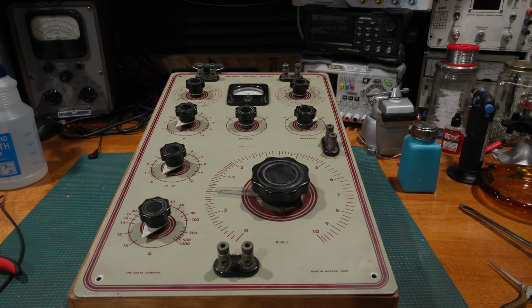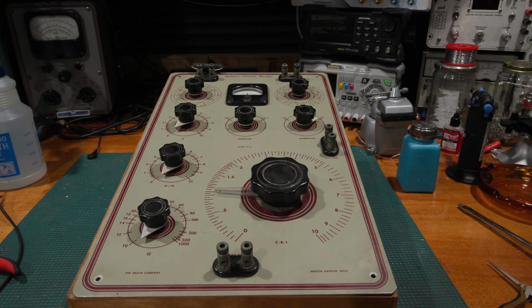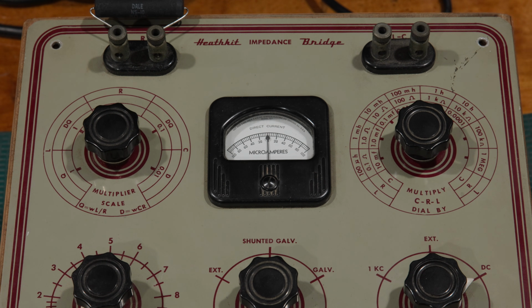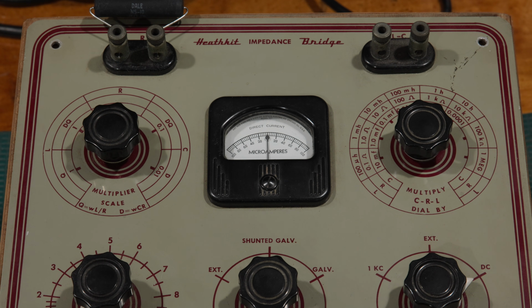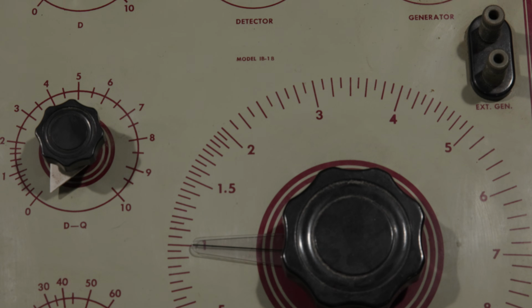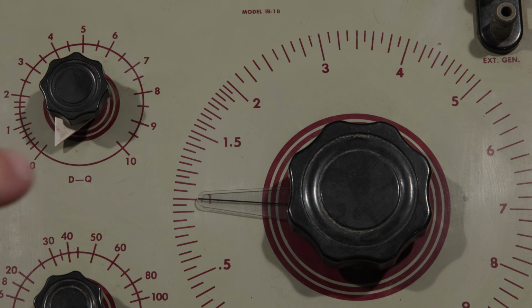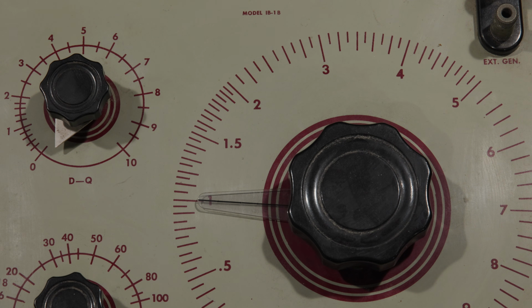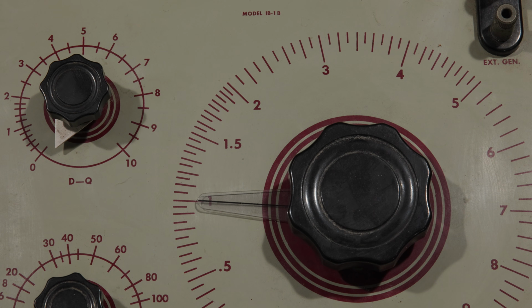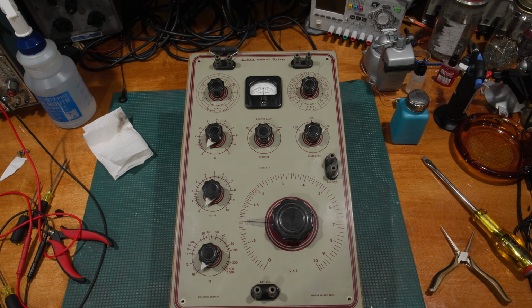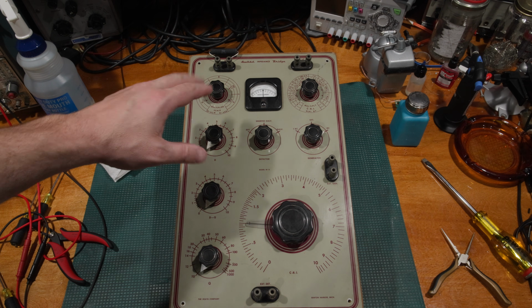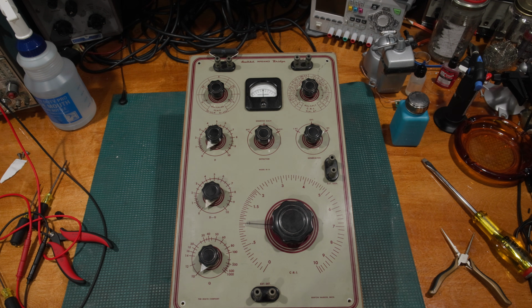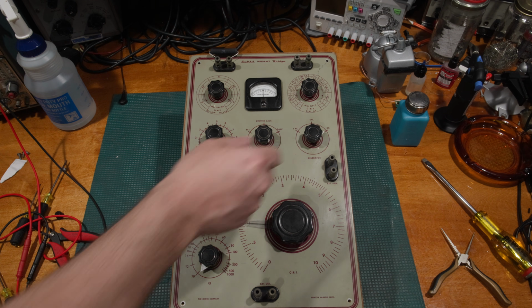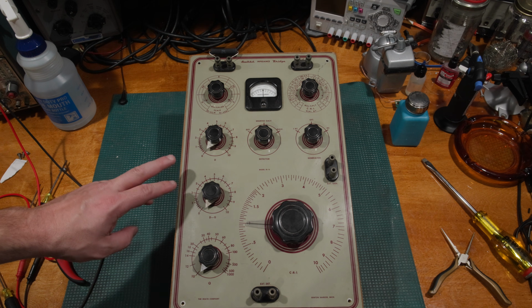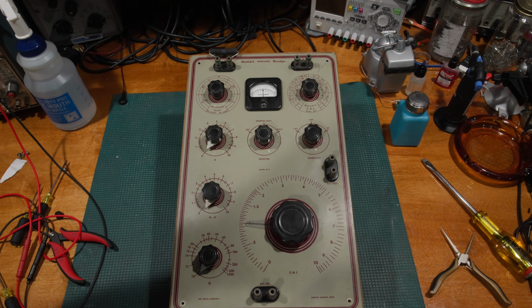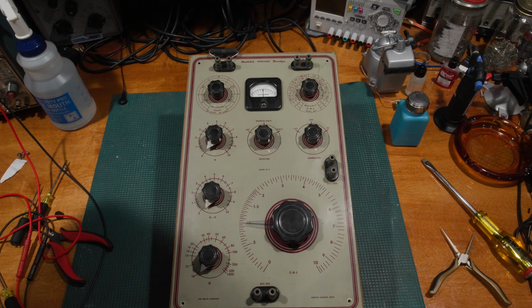So we'll leave it on, tweak the control, and then I'll show you guys a top view. I will kick it into operate, and as we can see, there was no deflection on the meter, which is exactly what we wanted. Now, pardon the pan. We are dead on 1. So this unit is now calibrated according to the service documentation. That being said, this unit is highly sensitive to the battery voltage, so as the battery voltage falls, that'll get a little out. But when it's in non-DC mode, external generator or external, it's not drawing on the battery, so it's actually off. So really happy with that.